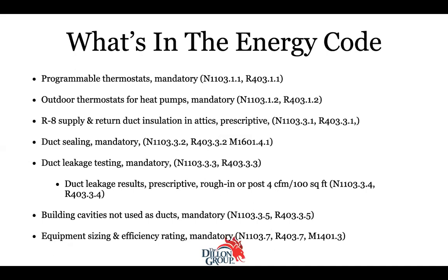And Texas had this weird thing where, if you installed a 14 SEER air conditioner, you could drop it down to R6 because we didn't have a lot of R8 around. But now R8 is just common as house mice. Duct sealing is mandatory. That came out quite a long time ago. The duct leakage testing, which the testing is now mandatory, that's been a fairly recent development in the codes. And the duct leakage test results, that's part of the prescriptive path.